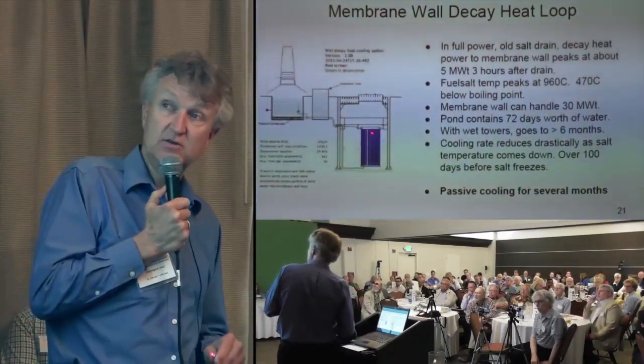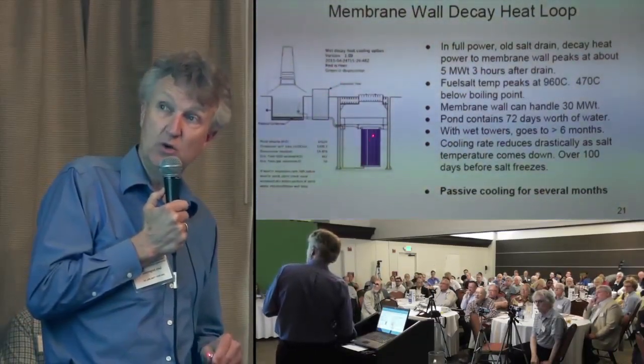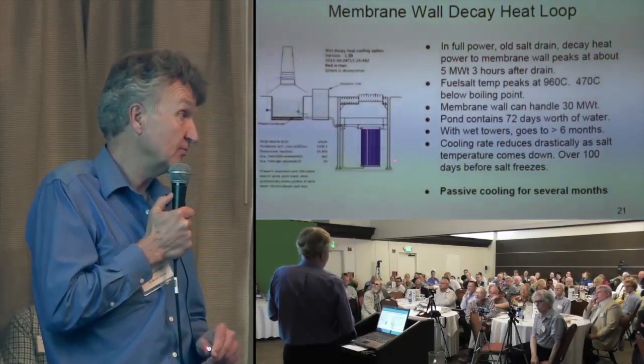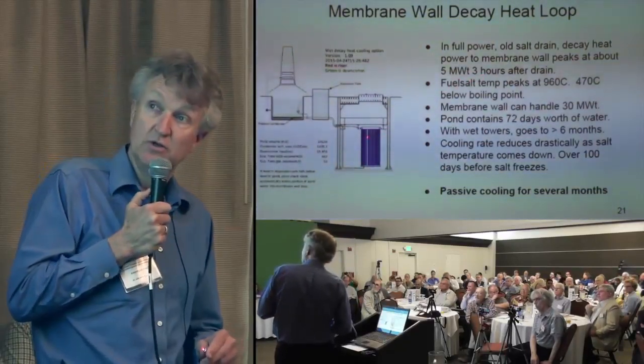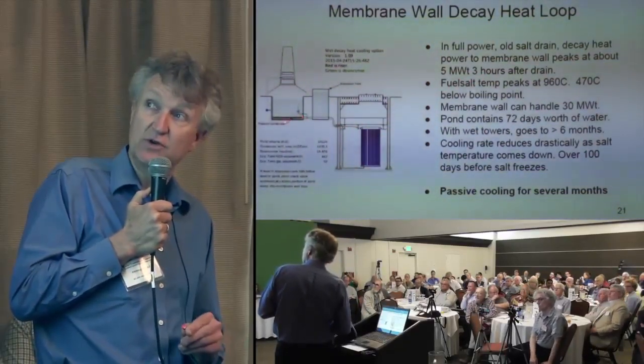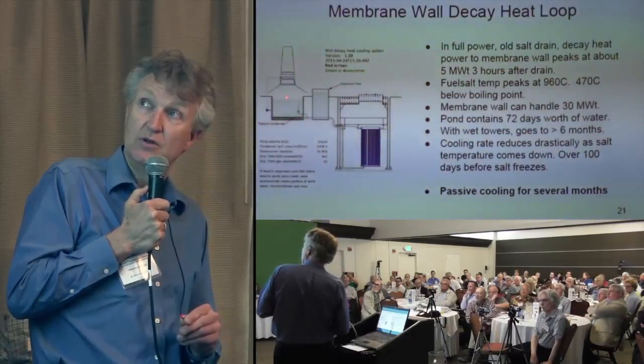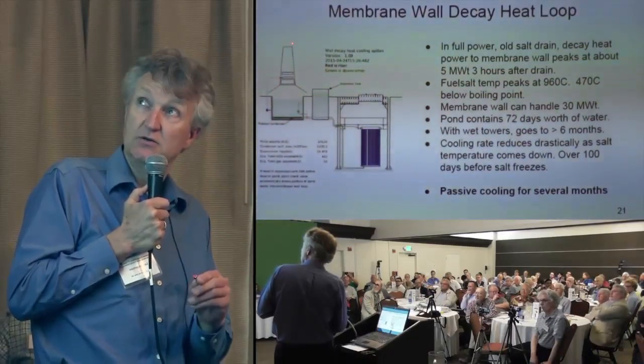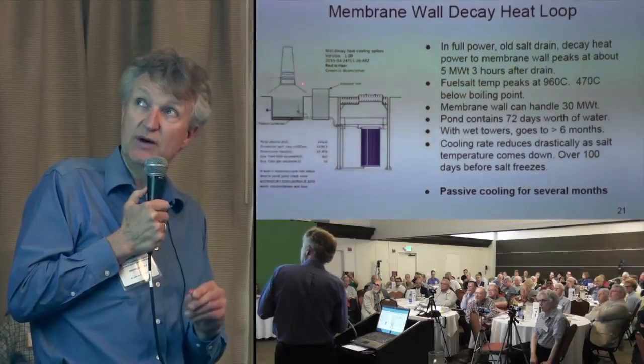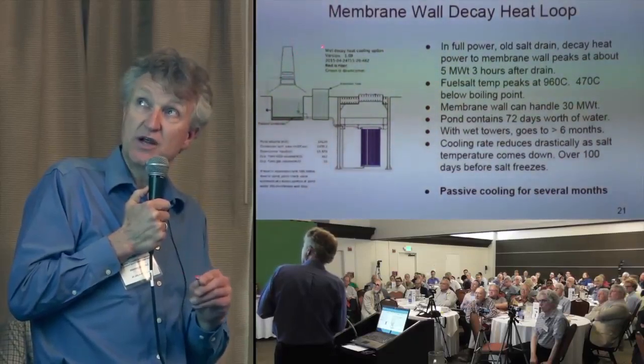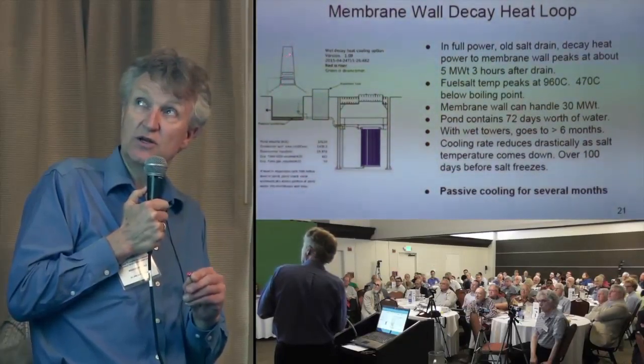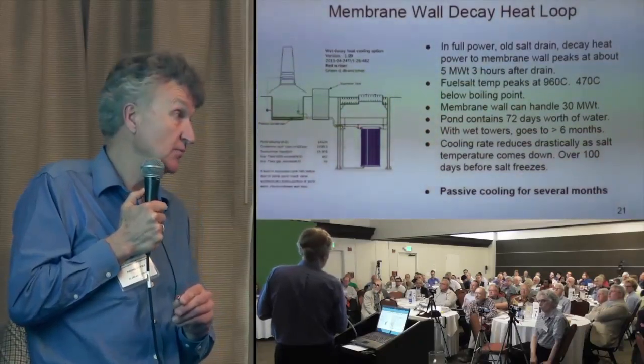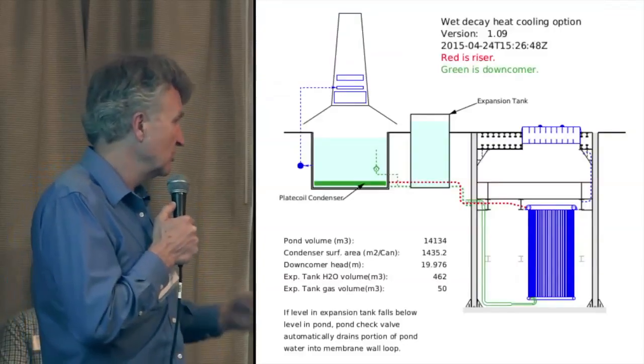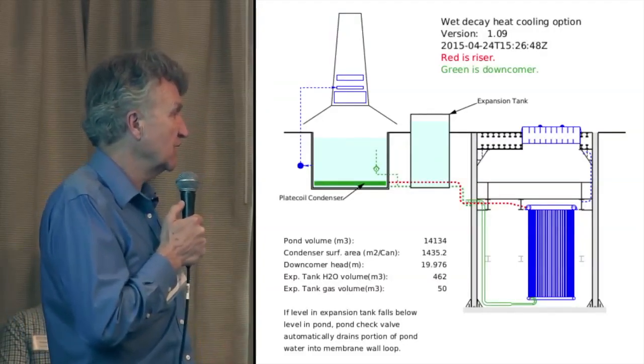Once we get the heat into the water of the membrane wall, we've got to get it further away because there's only so much water there. So what happens is the hot water travels over to a pond. The pond evaporates and goes up to a steel cone above it, a chimney, which is air cooled. The water condenses on there and falls back down again. That should give us nearly infinite supply of decay heat removal.